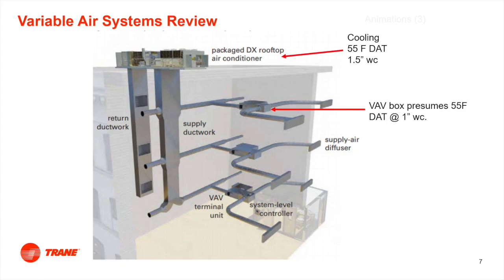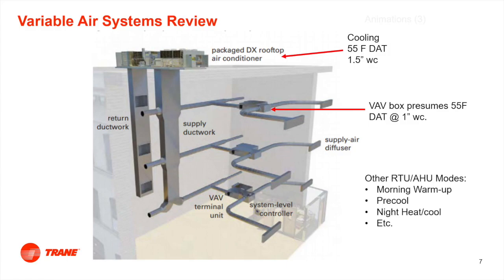Now a VAV box presumes that 55 degrees, that it's cooling. It also needs at least 1 inch static pressure. It does not know or care what the static pressure is, does not know or care what the air temperature is. As far as other things that rooftop air handler can do, yes, it can do morning warm-up, pre-cool, night heat cool, and a whole bunch of other things. But for today, we're just going to presume that rooftop air handler is doing cooling.